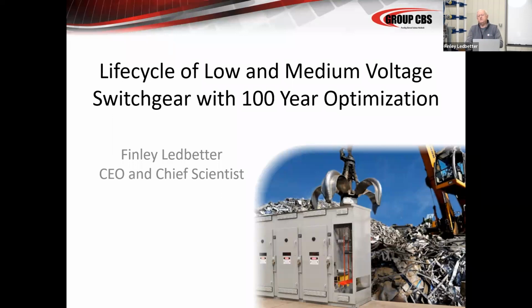And I don't know if anyone out there knows what the next big thing is going to be, what the next replacement for the vacuum breaker is going to be, but the solid state breaker, the nano and graphene technology, all the things we've been promised over the last years has not worked out. So there really is not a good, close to market alternative to the vacuum circuit breaker at the higher power levels. Now, sure, you can turn a solid state circuit on and off at a few thousand volts and a few thousand amps. But when we start talking about the newer breakers rated 50, 60, 70, even 80,000 amps interrupting ability, I think we're a long ways away from that with solid state technology. Consequently, I think we're stuck with the vacuum breaker.